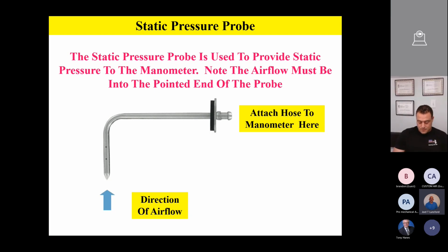Now, this is really, really important. Please make a note of this. Write this down. Put a smiley face by it, whatever you have to do to remember this. If you have a filter in the return ductwork right next to the air handler, make sure you take readings on both sides of the filter. Let me say that again. I like to take readings on both sides of the filter because that gives me some idea how much static pressure drop or how much static pressure difference I have across the filter.